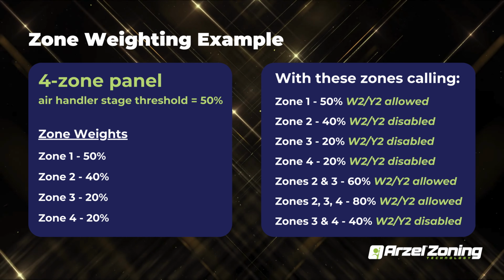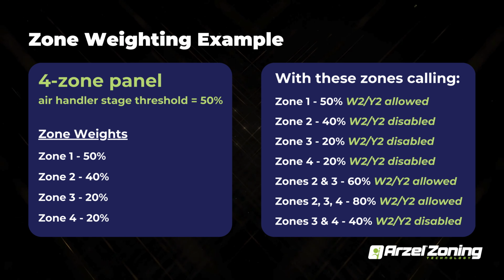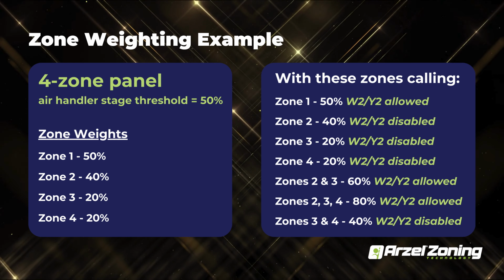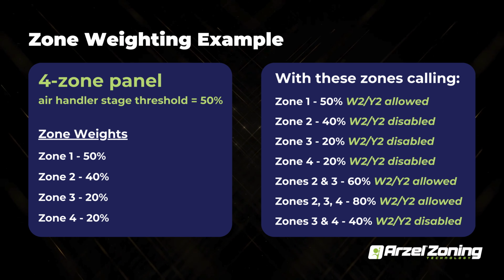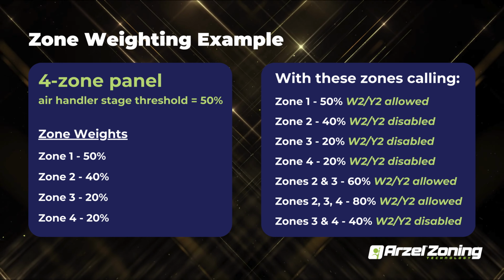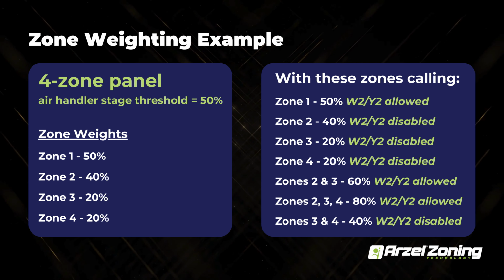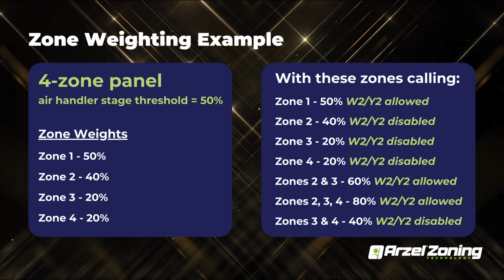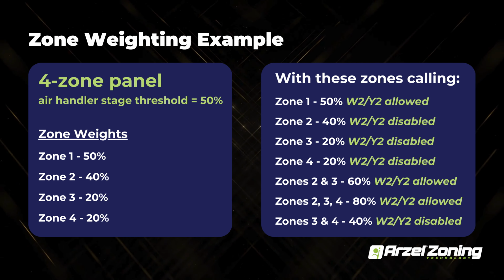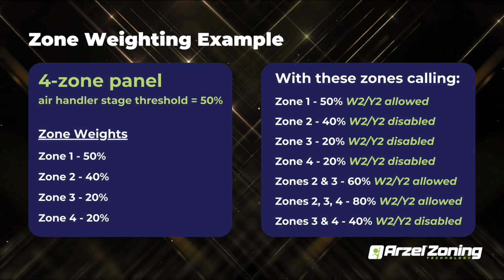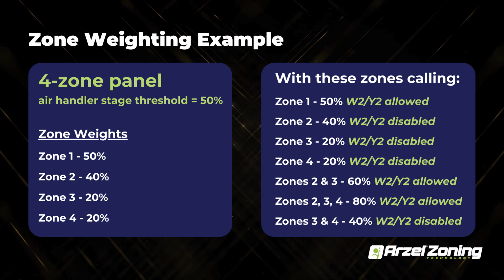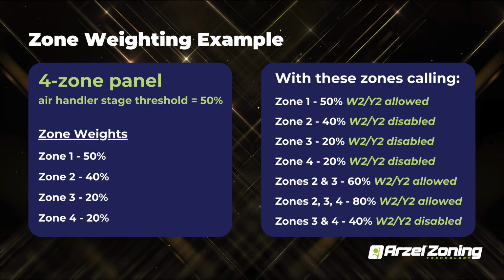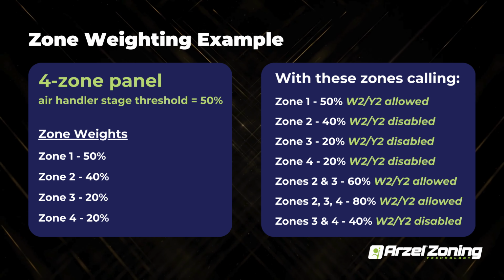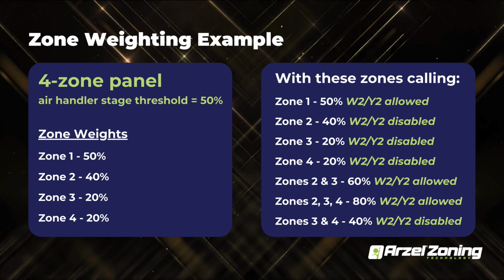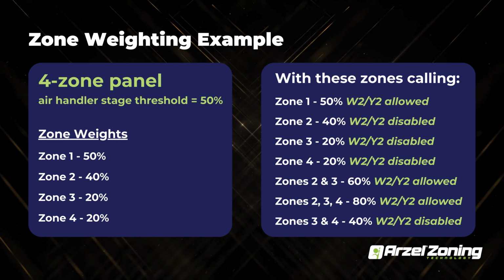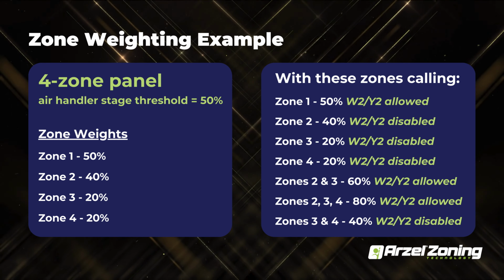And then when you're looking at zone 3 and zone 4, we both have 20%. So neither of these zones can go into second stage by themselves. They also cannot go into second stage if they call together. So if zone 3 and zone 4 call together, you're still not going to get second stage operation. But if any combination of zone 2 and zone 3, or zone 2 and zone 4 call together, you'll be able to get second stage. That's how you need to look at it. It doesn't really matter the percentage that you assign for that zone. It's more so, does it equal that air handler stage threshold, or is it less than the air handler stage threshold?